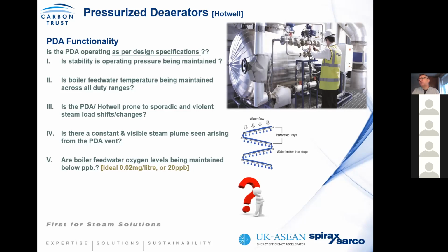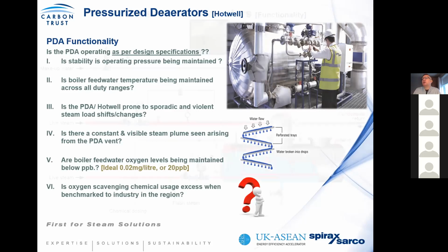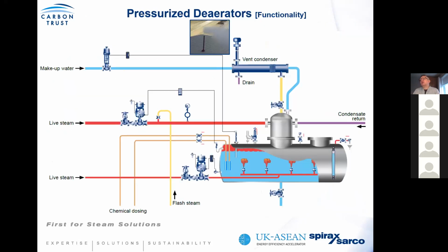And often there's a tendency to overcompensate with a lot of chemicals in the boiler, and all chemicals which are added in the boiler must be removed through TDS blowdown. So in other words, understand your oxygen scavenging.